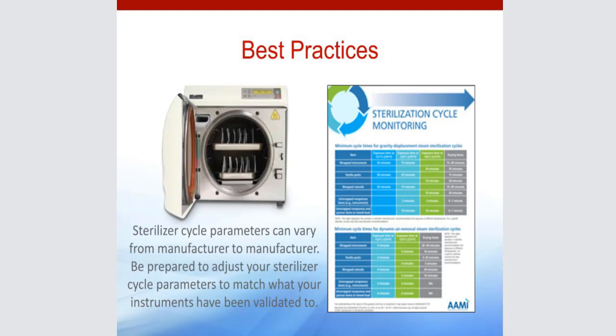We just talked about sterilizer parameters can vary from manufacturer to manufacturer. You need to know what each one of your cycles, what are the time, temperature, and pressure to make sure that it correlates with the instruments that you're putting in there. Heavier instruments may have a very different cycle process required than some of our lighter, finer instruments. Or if you're doing instruments that are hollow, that have lumens, that's going to have a very different processing time as well.